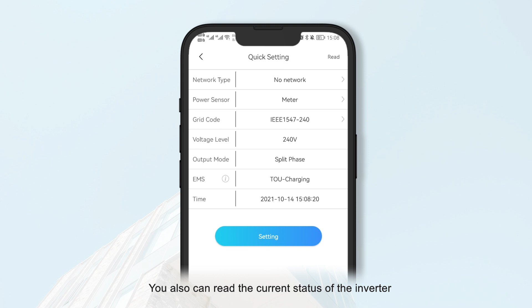The lower part of the interface shows detailed parameter settings. Quick setting includes the basic settings of the inverter: network type, sensor type, grid code, etc. We've gathered common functions for regional customers to simplify commissioning. You can also read the current status of the inverter.